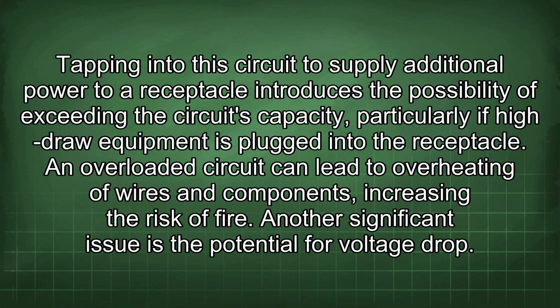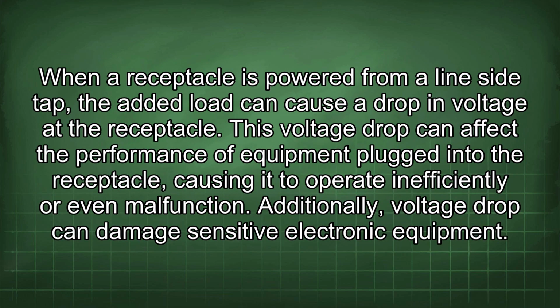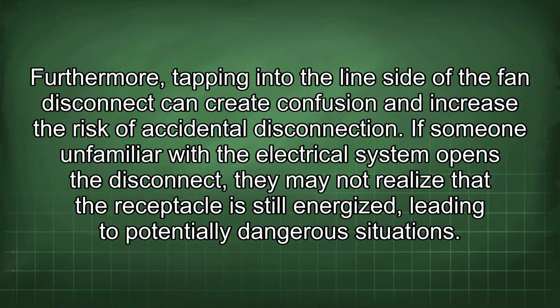An overloaded circuit can lead to overheating of wires and components, increasing the risk of fire. Another significant issue is the potential for voltage drop. When a receptacle is powered from a line-side tap, the added load can cause a drop in voltage at the receptacle. This voltage drop can affect the performance of equipment plugged into the receptacle, causing it to operate inefficiently or even malfunction. Additionally, voltage drop can damage sensitive electronic equipment. Furthermore, tapping into the line side of the fan disconnect can create confusion and increase the risk of accidental disconnection.